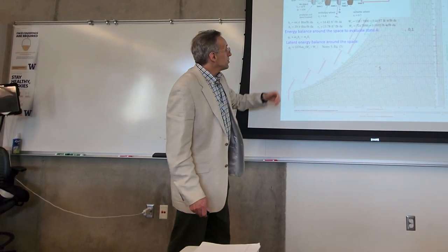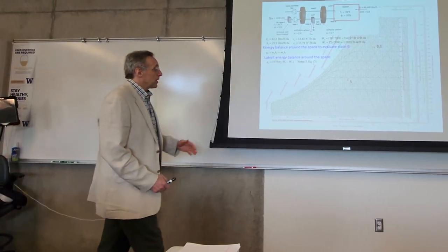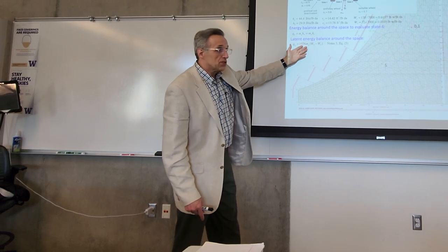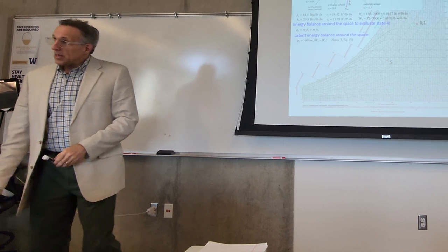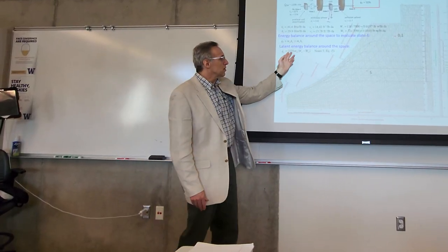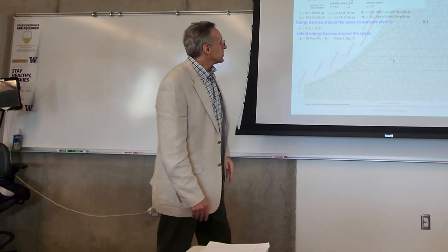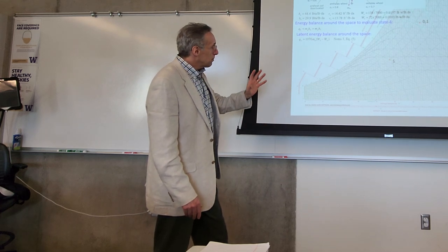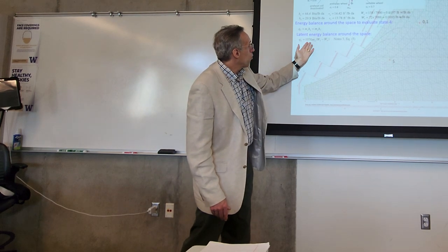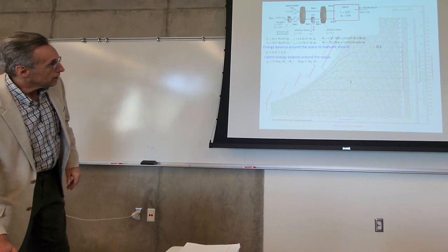And then the latent energy balance is, we're just balancing around the water component, where the latent load is 1076, which is the enthalpy of vaporization of water at, I think, around 60 degrees or something like that, at the temperature that's common, the ASHRAE standard for temperatures typical for HVAC conditions. And then the amount of water that's being evaporated. So that's our total and our latent balance.